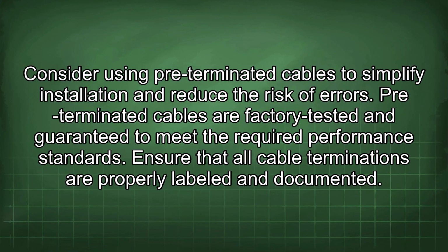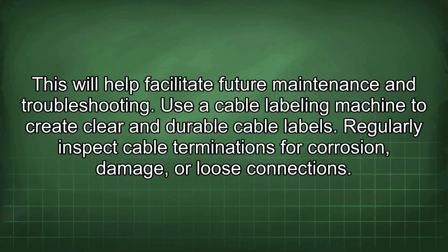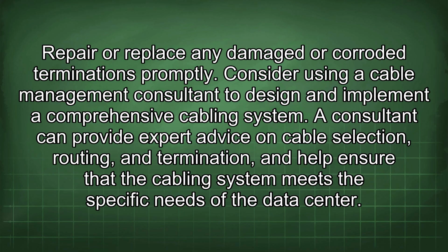Ensure that all cable terminations are properly labeled and documented. This will help facilitate future maintenance and troubleshooting. Use a cable labeling machine to create clear and durable cable labels. Regularly inspect cable terminations for corrosion, damage, or loose connections. Repair or replace any damaged or corroded terminations promptly.